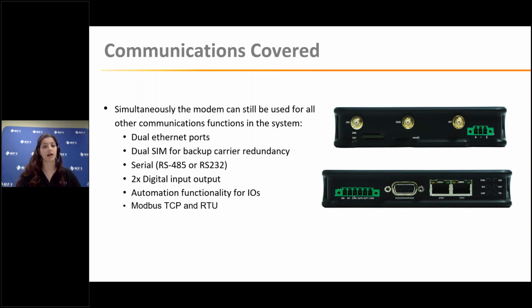They provide that internet backhaul, all cellular modems with generally upwards of Cat4, so they're providing high speed. They're able to handle everything on your site basically. We've got dual Ethernet ports, so you could put two direct TriStars or EMCs directly into that modem, or connect it to, say, another PC or another Ethernet asset on that site. So you could potentially use it not just for running your solar system, but also for another Ethernet Modbus or Ethernet application on that site.